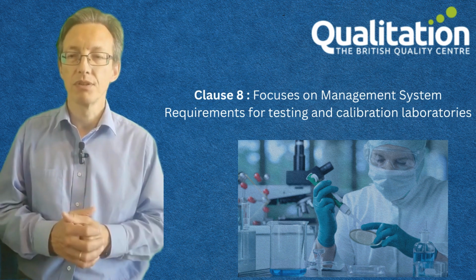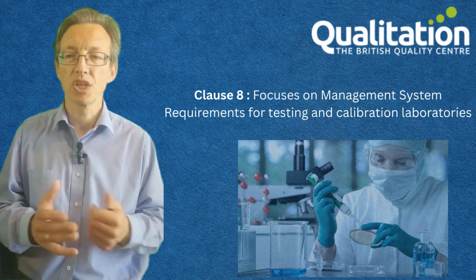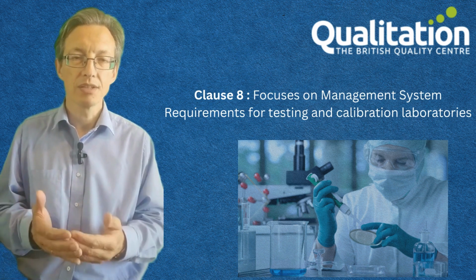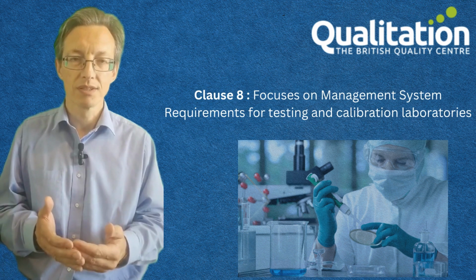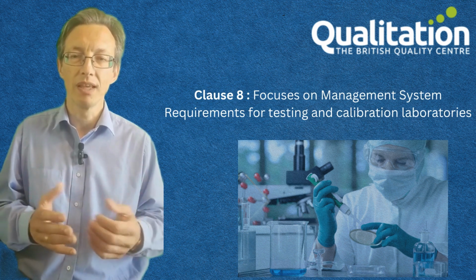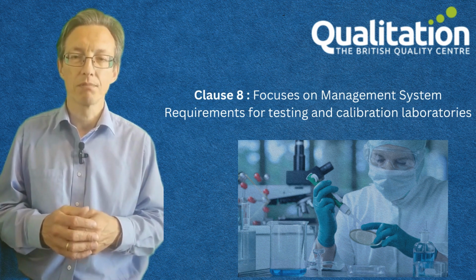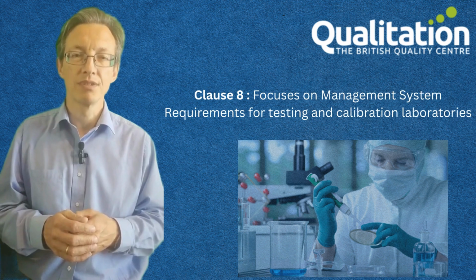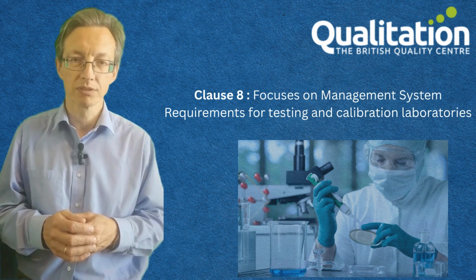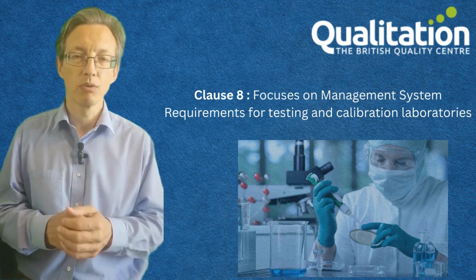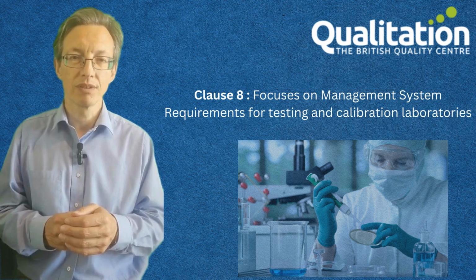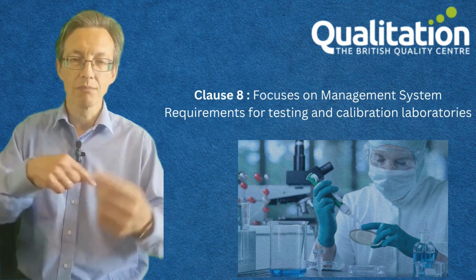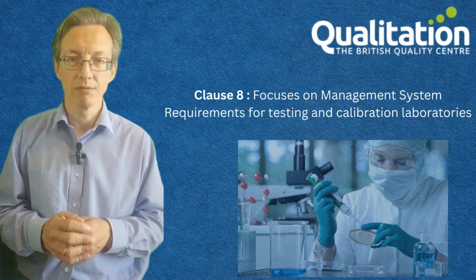The consultant's approach here is to establish an audit program with checklists and timelines. The checklists are to ensure that nothing gets missed. The timelines are to ensure it happens regularly. But ultimately, the benefit of the audit program is the results, not that there's a tick box. It's vital that people apply thought. Different people look at different things at different times on a rotating basis because different eyes see different problems.